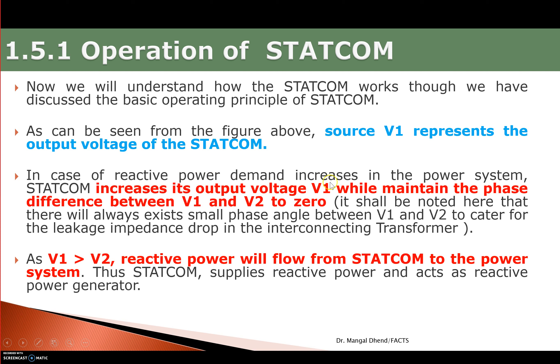When reactive power demand of the transmission system increases — for example, during peak or full load — the reactive power generated in the generating system is less than the demand. In such a case, STATCOM must generate and supply reactive power to the system. So when reactive power demand increases, STATCOM increases its output voltage V1 so that power flows from STATCOM to the system.